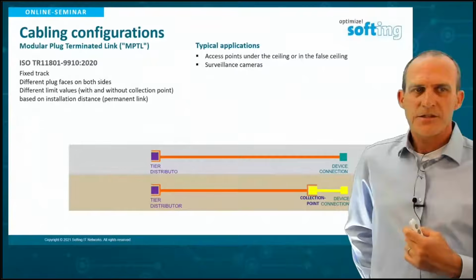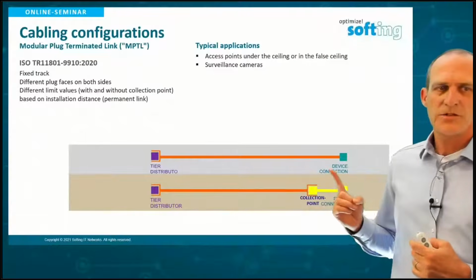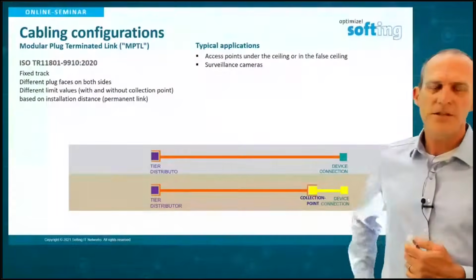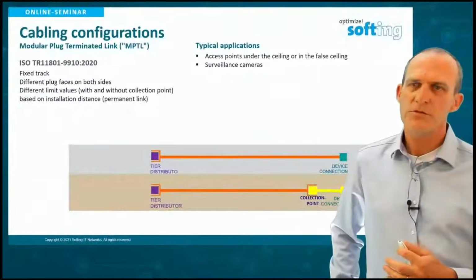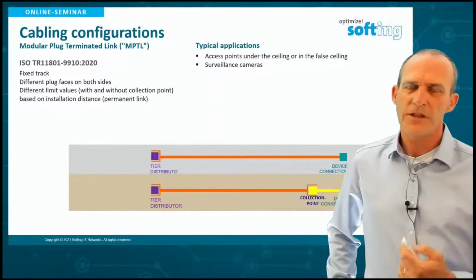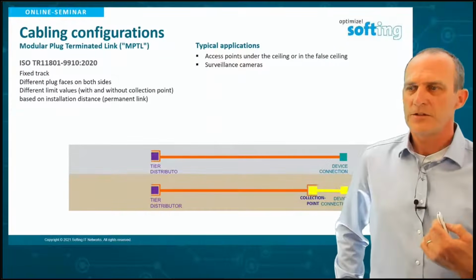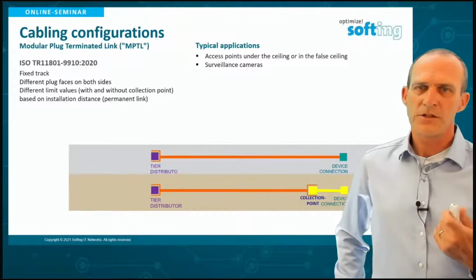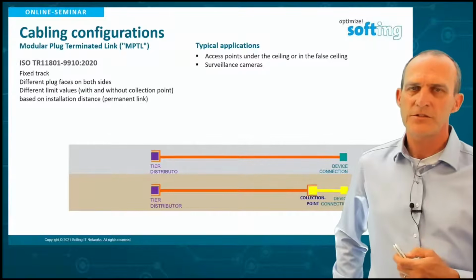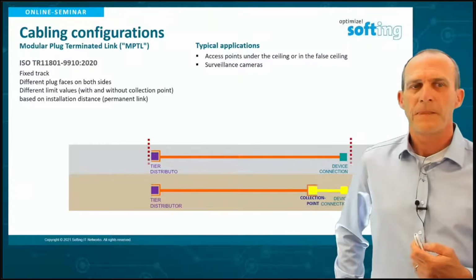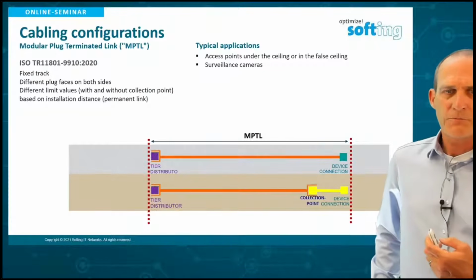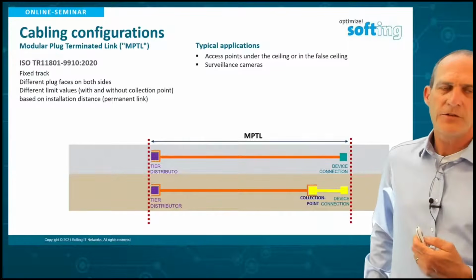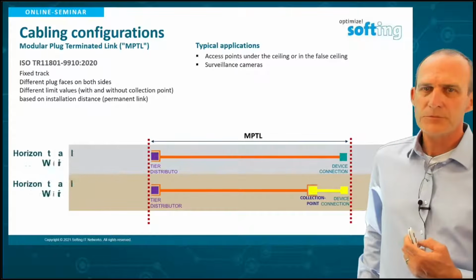In many cases, this plug you see on the device end is a field terminated plug. That also makes testing on that side really an issue, because your tester must include the first and last connector in testing. So you see where the reference planes are - they connect the first and last connector.